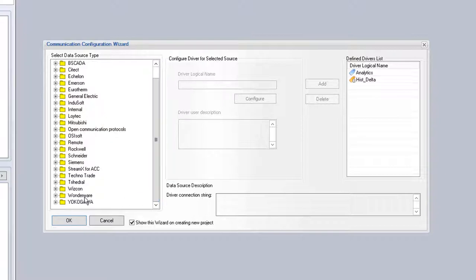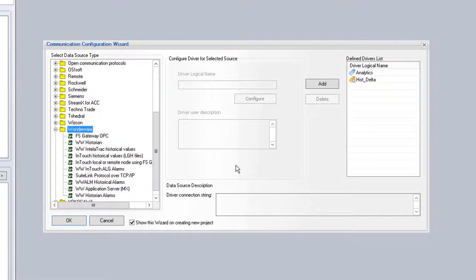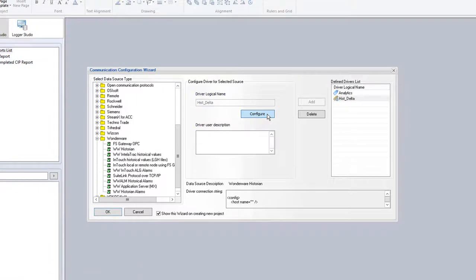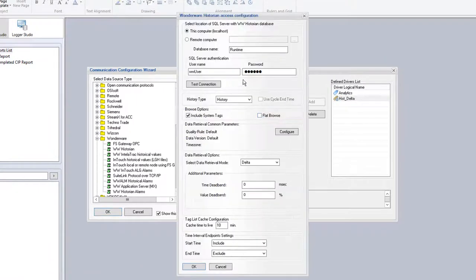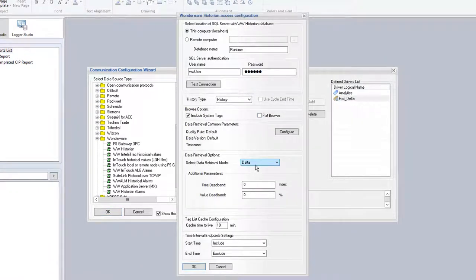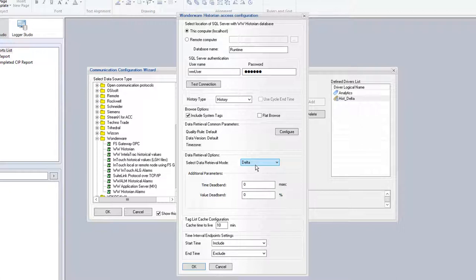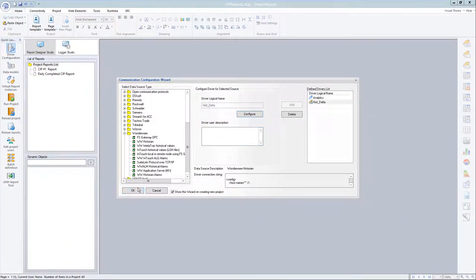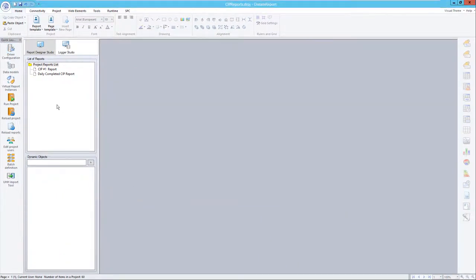I happen to be using a Wonderware historian on this VM, so I've configured the driver in DreamReport to connect to this historian using the Delta data retrieval mode, which is the preferred way for points that need to be retrieved on change, like CIP ID, CIP status, set point changes, etc. We might also want to set up another connection to retrieve data periodically, for example every 10 seconds for temperature flow and conductivity PV values. That's really dependent on your needs for the charts or tables.